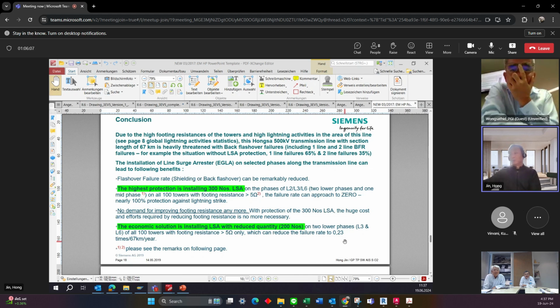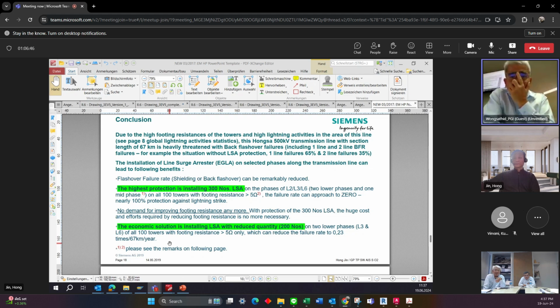That is also the line study simulation result. Hongsa says in their area they have only 67 kilometers of line. And if they install only 200 pieces, then based on the simulation, the failure rate will reduce to 0.23 times per year in their area, 67 kilometers. But the total line length is 67 kilometers only, right? I think this is the length of Hongsa's responsibility. The other responsibility belongs to EGAT in the Thailand area.